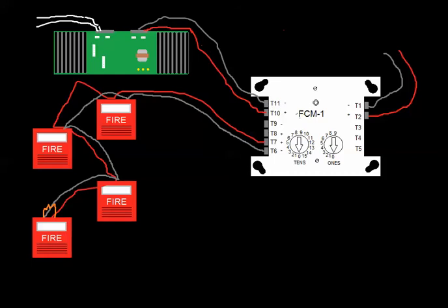But through programming, maybe you don't have the control module turned on. So if somebody were to pick up the microphone on a manual evacuation system and start talking, the amplifier would amplify that signal and it would go to the control module, but again, through programming, maybe that control module is not turned on. So there's a couple different components. It works generally the same way as the strobes. The important thing that I want you to take away from this is there's a different input to the control module than in the strobe or horn strobe scenario.